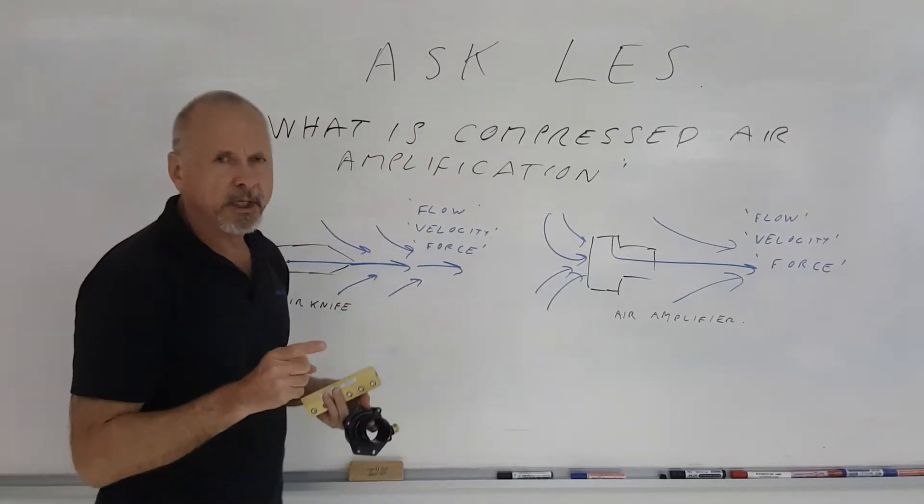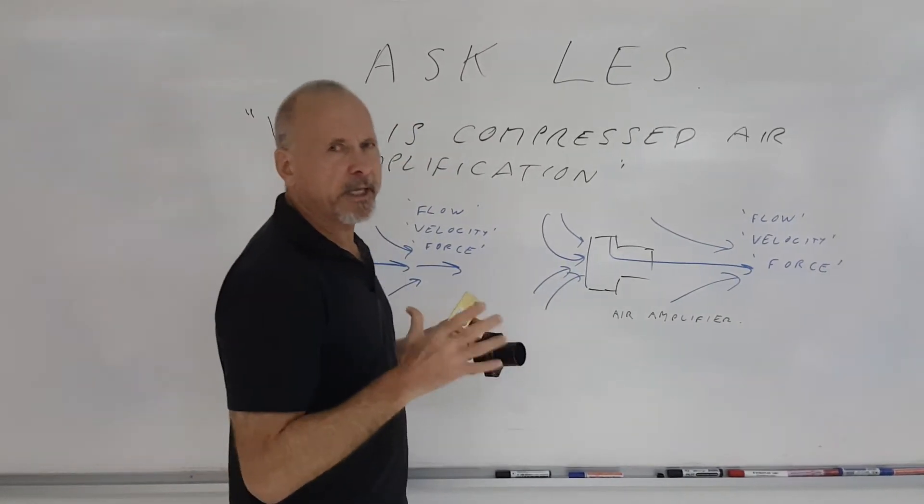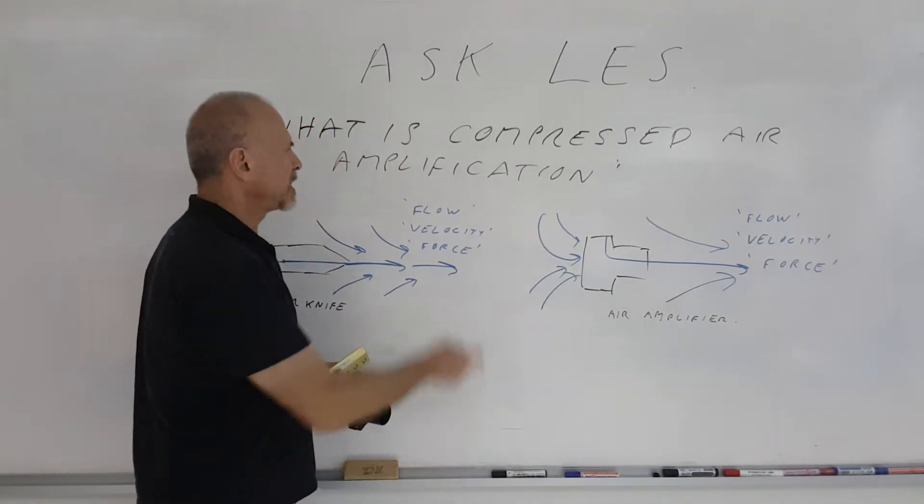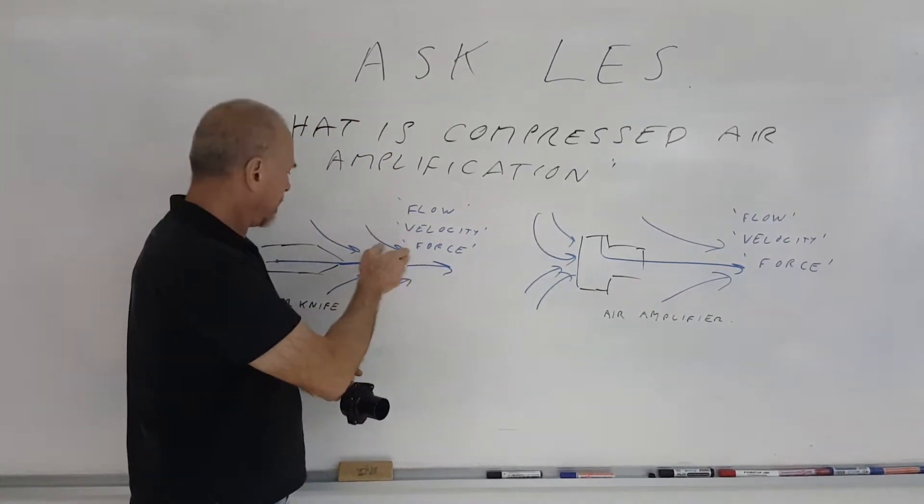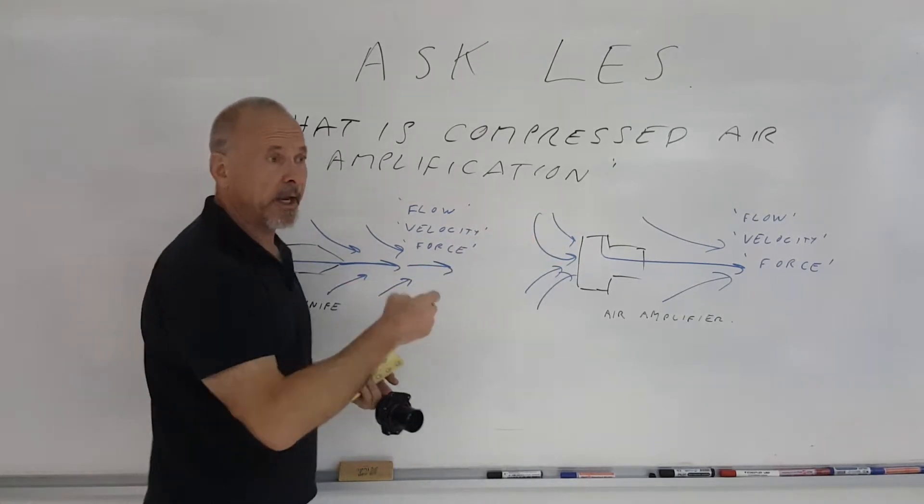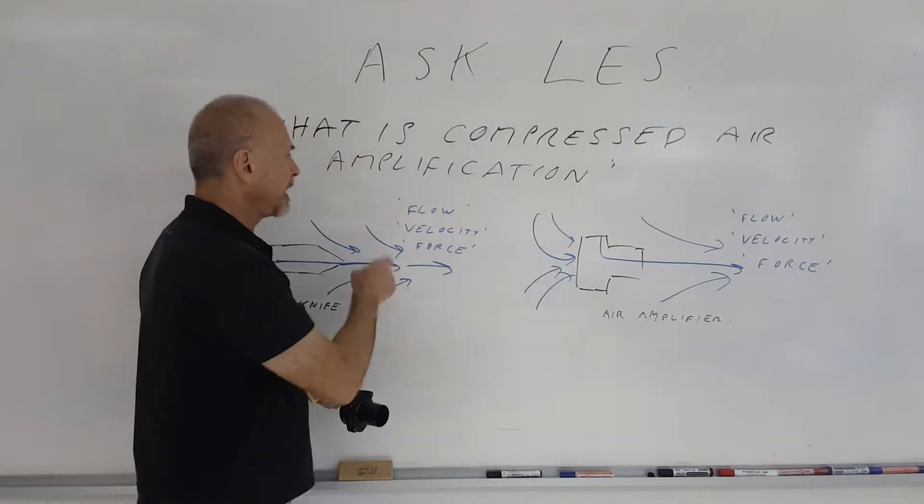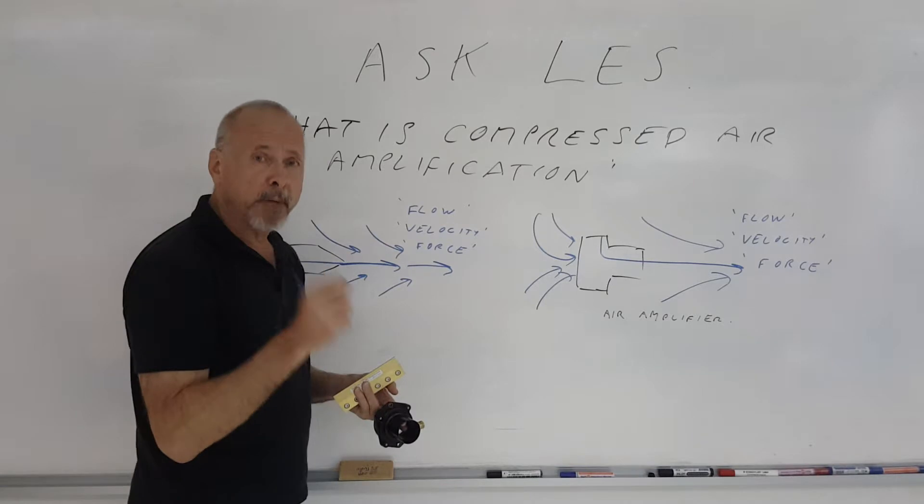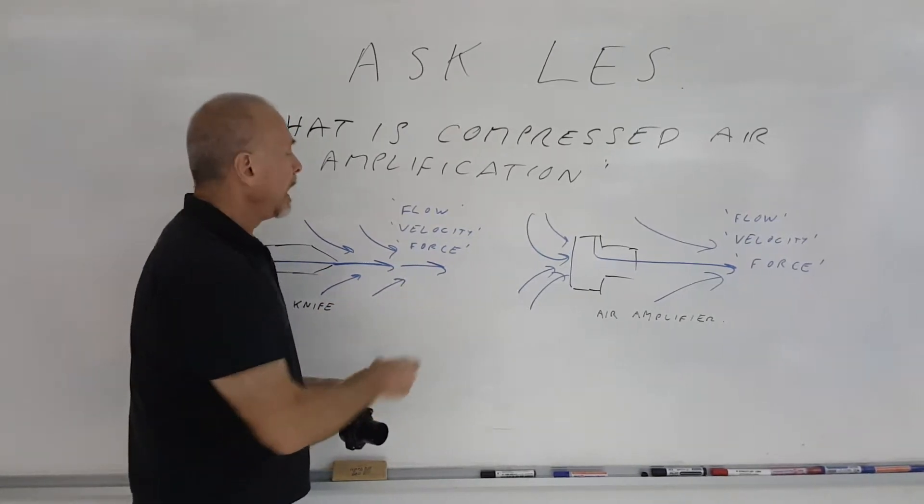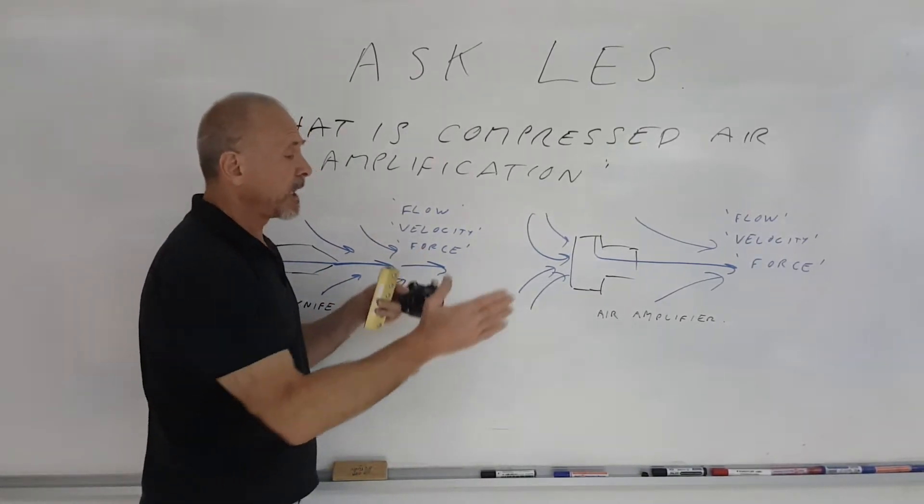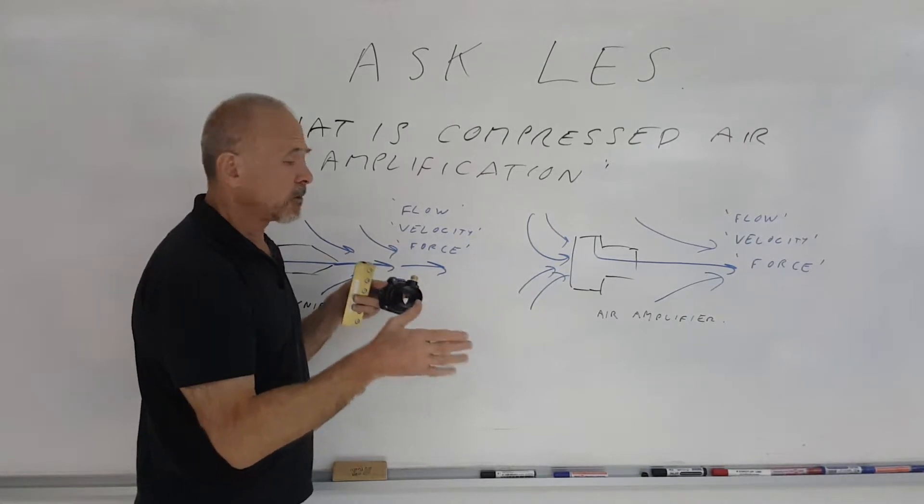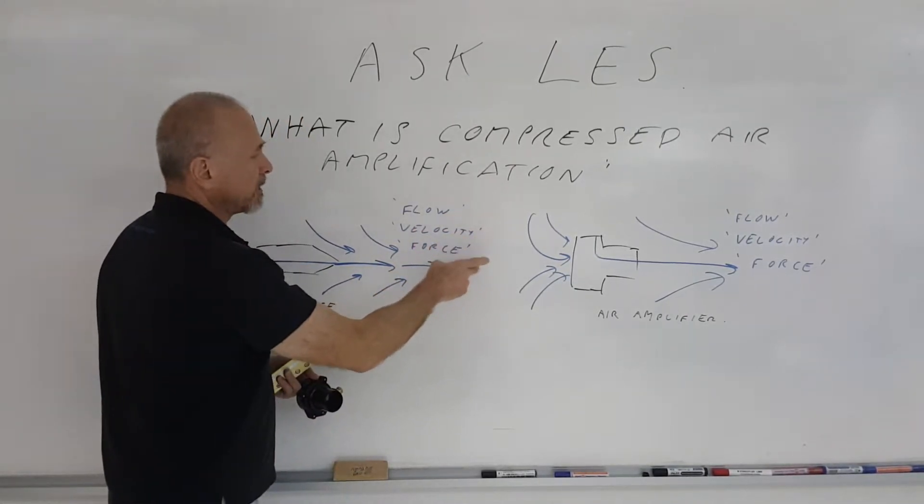What you should be looking at is not the figure for air amplification. You should be looking at the actual output flow which can be measured from an air knife, amplifier, and nozzle. You should be looking at the actual velocity which can be measured by a velocity meter, and of course the force which can be measured by a simple scale. This is what's really important because that's what's going to determine how effective the unit really is.